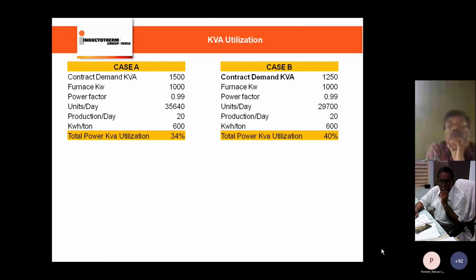Similarly, case B: if I reduce the kVA, let's talk about 250 kVA. If you surrender that power, it means nearly 1 lakh per month. I'm not sure about the exact level, you can cross verify at your end. The furnace kilowatt is 1000 and power factor is 0.99. The units allotted are 29,700 since you are reducing your contract demand. Still you can produce the same tonnage as in case A, so the utilization of your kVA goes up to nearly 40%. Does it serve the purpose? No, absolutely not. We still have the cushion to improve our utilization.